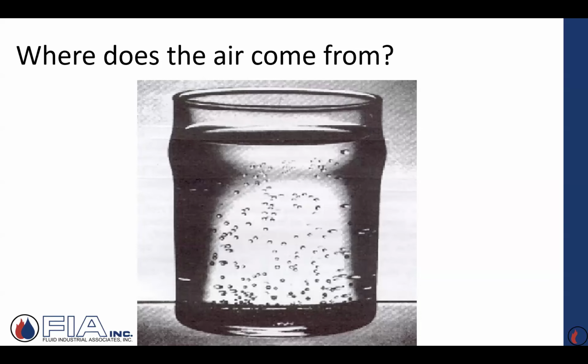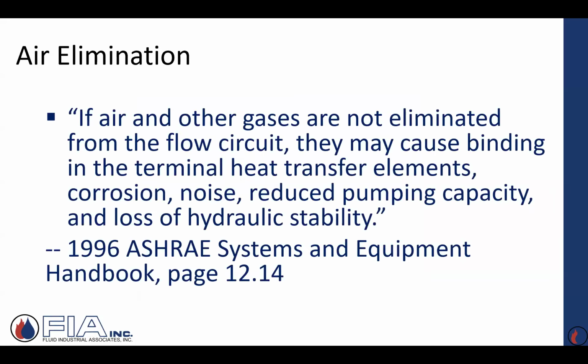Well, it's a very, very simple picture. It's actually out of one of the manuals that are either online or that the people here in the classroom have in their engineering binder. Just simple tap water. You fill in the system, H2O. There's oxygen, and oxygen can stay in solution based on pressure and temperature. As you heat the water or lower the pressure, it can't hold as much air. Air can't stay soluble, so it comes out in bubble form. So just simply filling a system and then heating it, especially in a boiler plant, you're going to have air coming out. So we want to make sure that air doesn't become a problem.